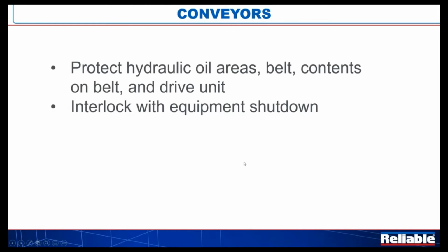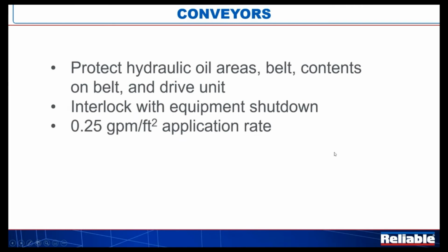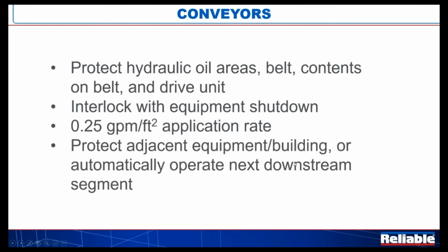So we're going to interlock that with the equipment shutdown. Minimum application rate of 0.25 GPM per square foot. And then we also want to look at where this material potentially could end up. Is it going into another building? If so, that building needs to be protected. It makes sense, but they just have to give us the rules anyway.